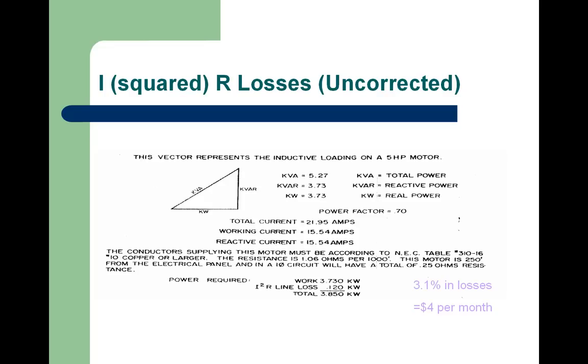Okay. This is an example right here. The I squared R losses uncorrected is an example that was done years ago. This is a 240 volt system, single phase, but just to give an idea of what the I squared R losses could be. In a case like this, we have a 5 horsepower motor, and if we go back to our original power factor being the kilowatts divided by the kVA, we have a power factor of 70. We're actually using a total of 21.95 amps if you were to take a meter on that. And if we broke out those amps between the kilowatt amps, if we could call it that, and the kVAR amps, magnetizing energy, these are the two values.